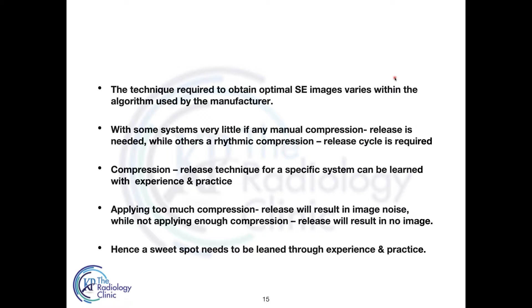Applying too much compression release, pressing so hard and releasing, will lead to image noise. And when we are not applying any compression release, it will result in no image. Hence there is a sweet spot: how hard to press, how much compression release to give, and at what rate. That sweet spot varies from machine to machine, and it can be learned through experience and practice only.